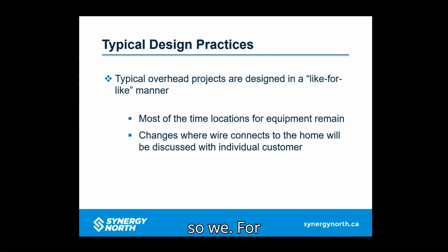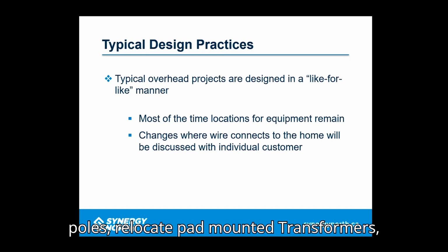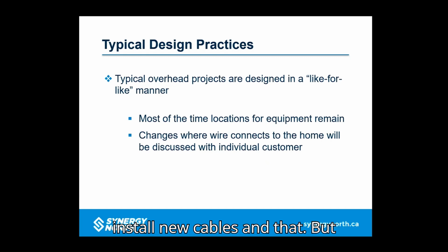Typical design practices: for overhead and underground projects, we attempt to design and construct them in a like-for-like manner. This means keeping equipment such as poles, anchors, and transformers as close as possible to the existing location. There are times we need to make changes though, for safety reasons, clearances to houses, or to meet new codes and standards, so we sometimes have to relocate poles or pad-mounted transformers and install new cables. But we try to be as least disruptive as possible by reusing existing locations.